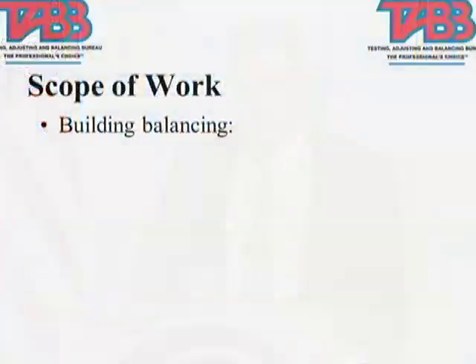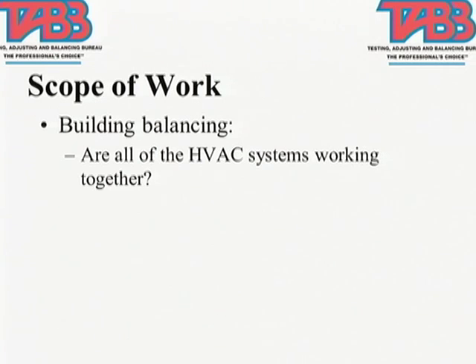Scope of work, I like to talk about this. The balancer comes in and says, what are we doing as the building balancer? They do not come in and say, are all the HVAC systems working together? This hotel is a great example. If you come down the hallway and you feel a rush of air coming towards you, the first thing people would say is, this building's not balanced. But when the balancer came in, they only did it to design specifications. They don't take into consideration if the engineer said, this is a windy area, most of the time we're going to have a 20-mile-an-hour wind from the northwest, and as it's hitting the building, I want to pressurize this side of the building. So the balancer never really looks at the entire building and says, I'm balancing the building. I'm only balancing the terminal device and what's on the design.